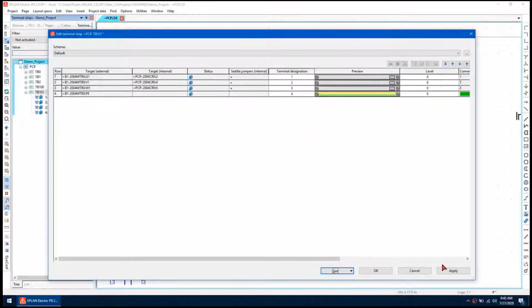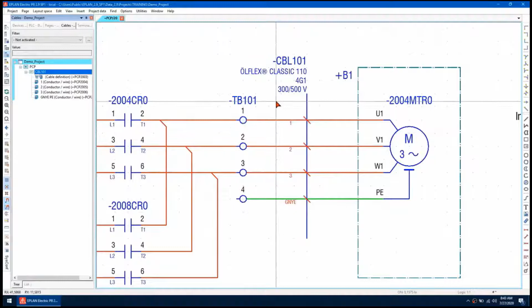What we can do is sort the terminal strip based on numeric values here, and then hit apply. Now to update the cable, we go to the cable navigator, right click on our cable, and go to assign cable connections and reassign all. Once we do this, we get the correct sequence of conductors.